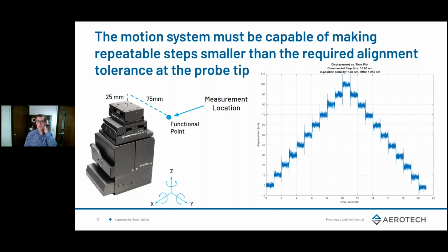In this case, you can see that over our 10 nanometer steps, 10 forward and 10 back, the worst case repeatability is actually at the 0 position, which is not surprising because it's the longest distance traveled. You can see here that we start at 0 with about plus or minus 3 nanometers of noise, and we end at approximately negative 4 nanometers. So in this case, over our 100 nanometer distance, we have approximately a 4 nanometer bidirectional repeatability. This gives us confidence that not only can we resolve the optical sensitivity of the system, but we can also return to the optimum.